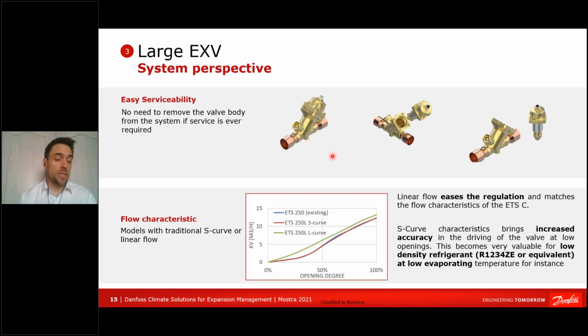I was also discussing the flow characteristic, and I will insist on this one because I think it's quite important to really understand why it's good to have both. We now have a common trend along all the valves in the ecosystem, which is a linear flow characteristic. You see here the green curve. So the opening degree versus the KV of the valve is linear. Historically, we had that S-shaped curve.